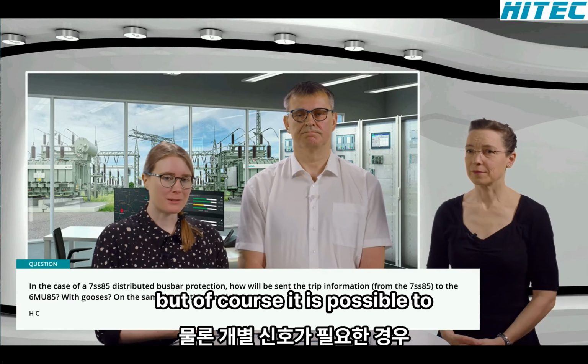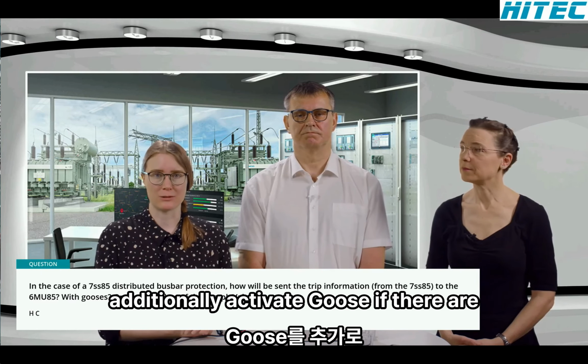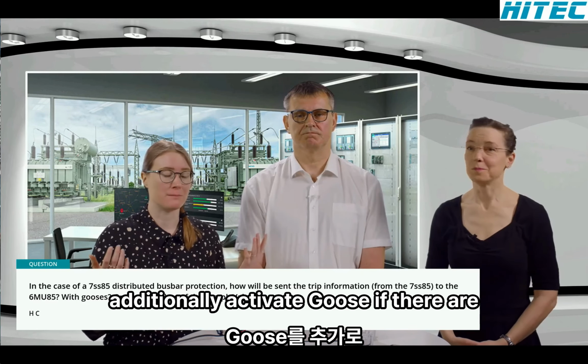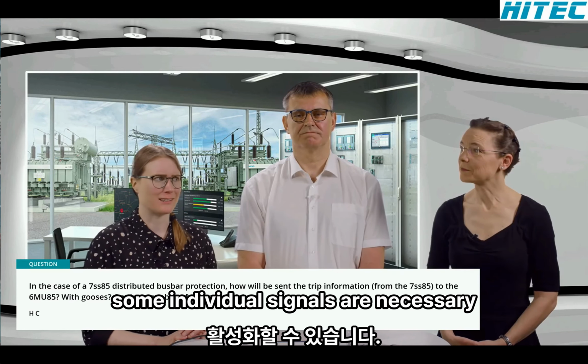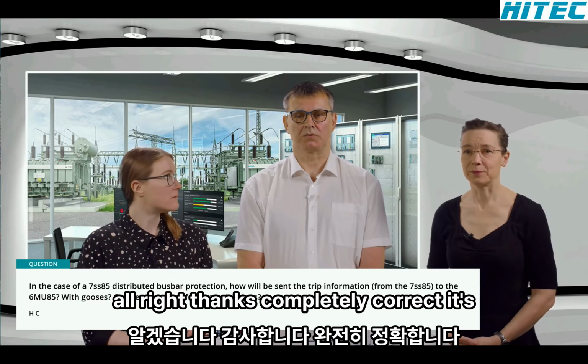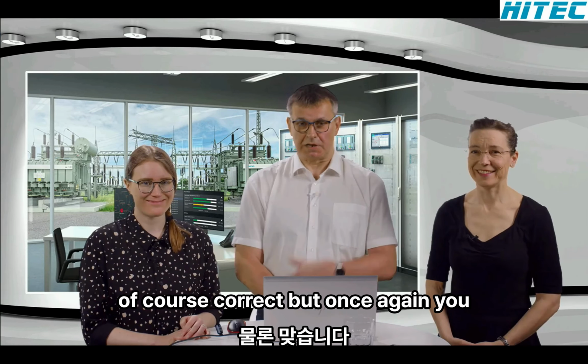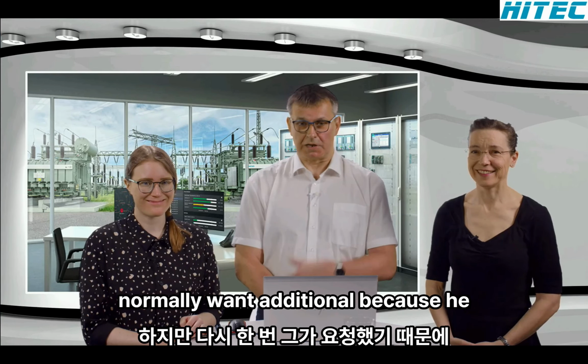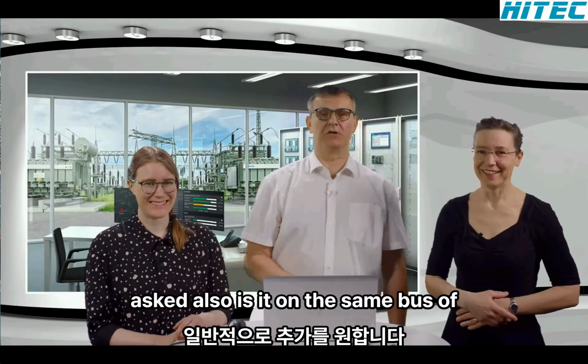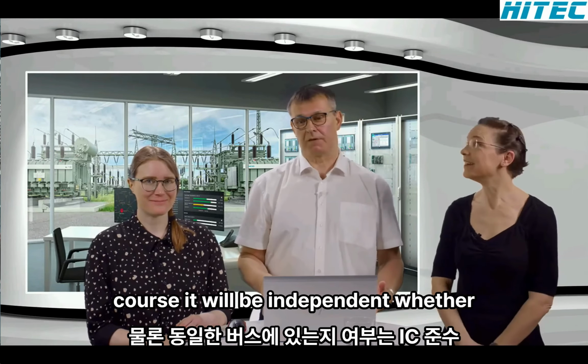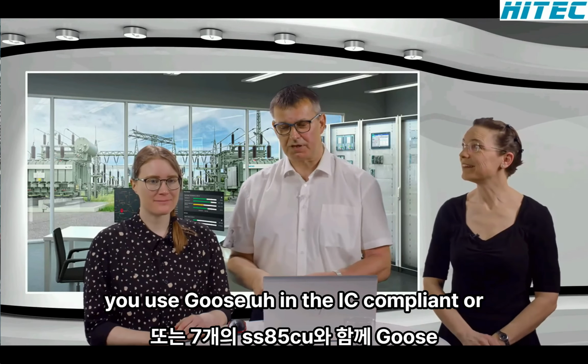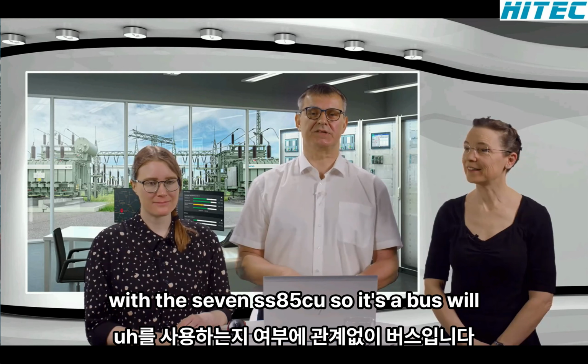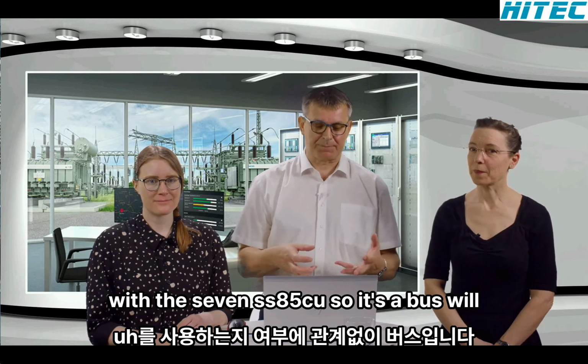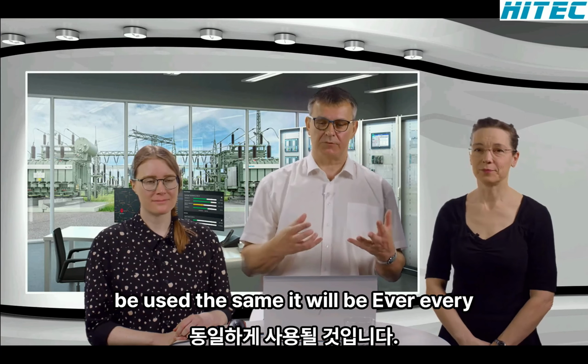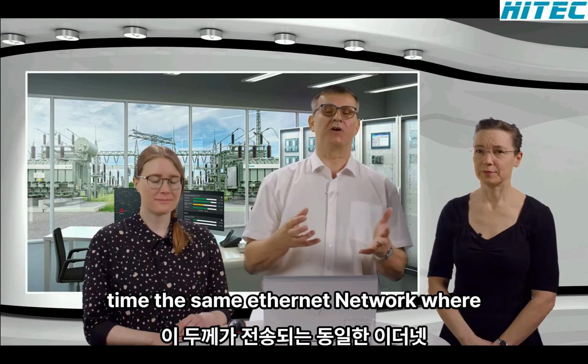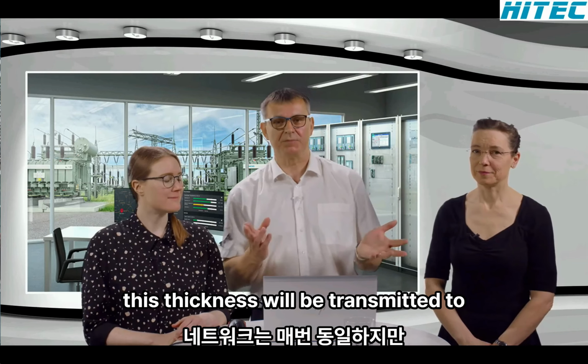But of course, it is possible to additionally activate Goose if some individual signals are necessary. All right, thanks. Completely correct. It's of course correct, but once again, you know me, one additional point, because he also asked, is it on the same bus? Of course, it will be independent whether you use Goose in the IEC compliant or with the 7SS85CU, the bus will be used the same. It will be every time the same Ethernet network where these signals will be transmitted. The bus will be every time the same.